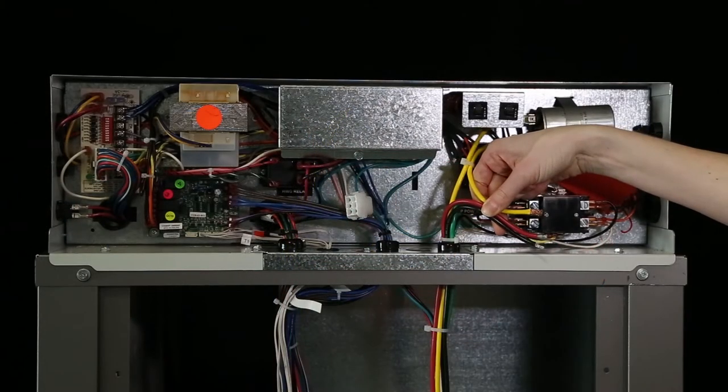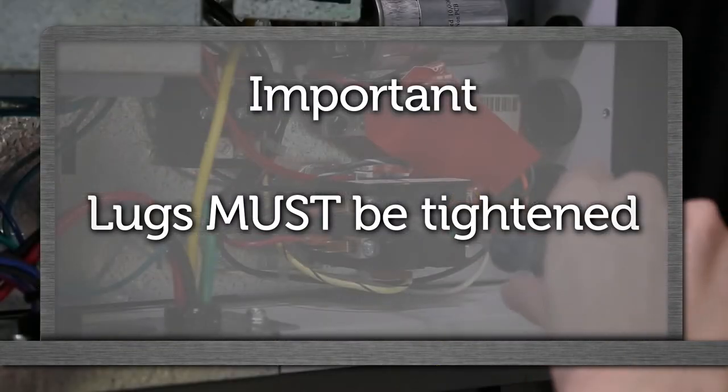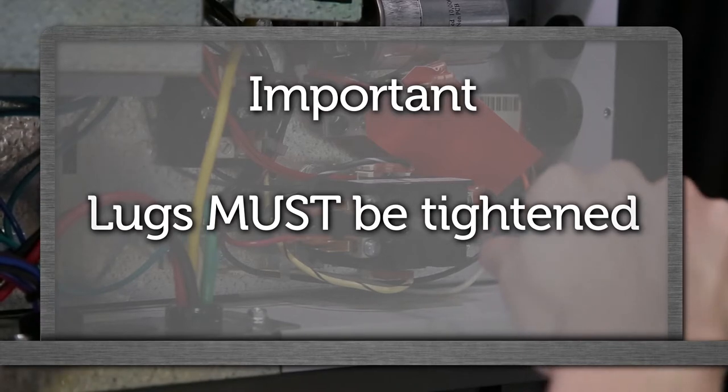Warning, this is important. After disconnecting the black, red, and yellow wires from the compressor contactor, the lugs must be tightened down or connection may be bad.